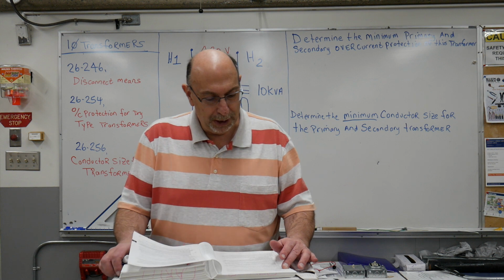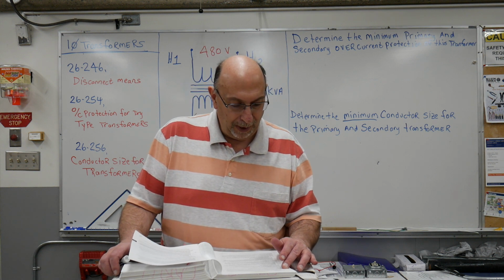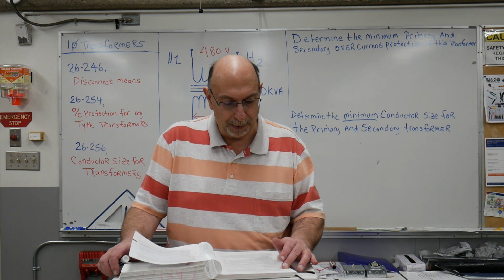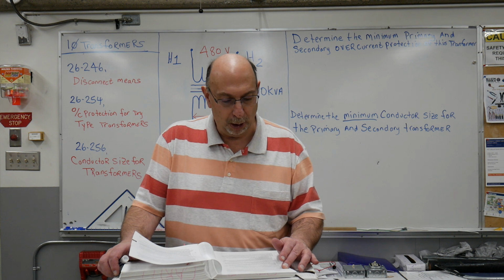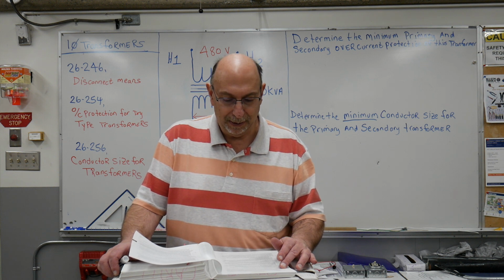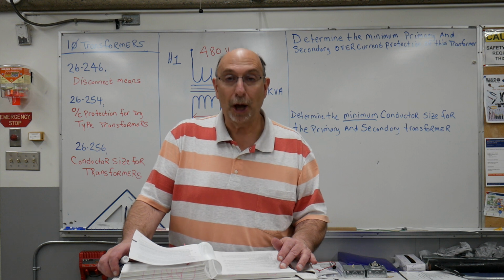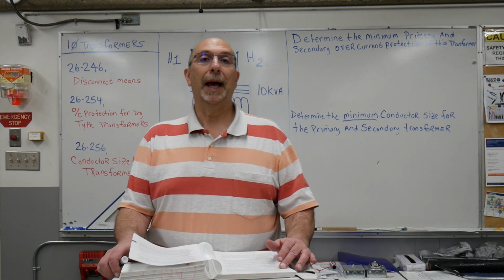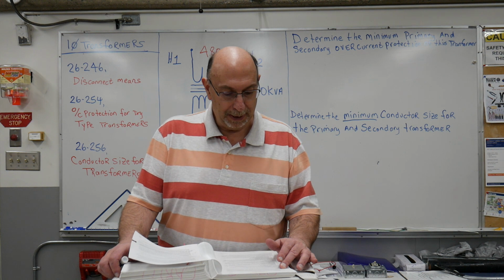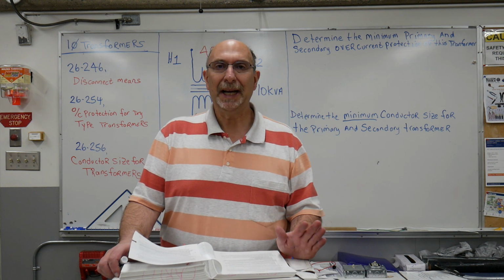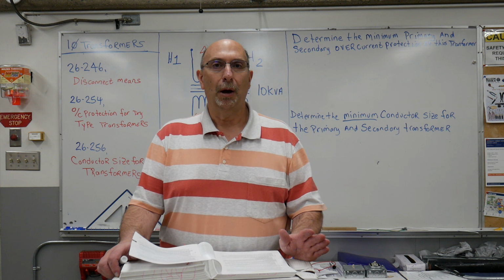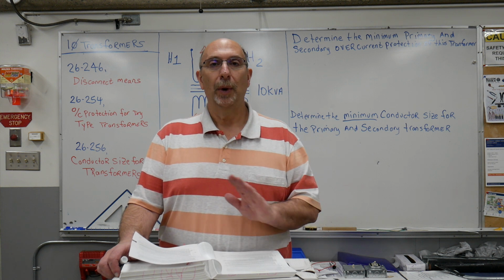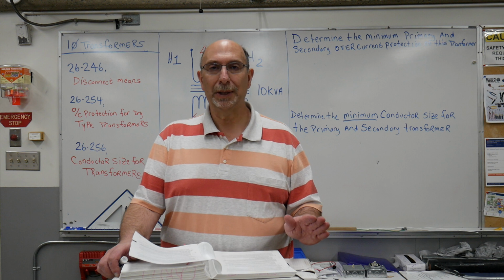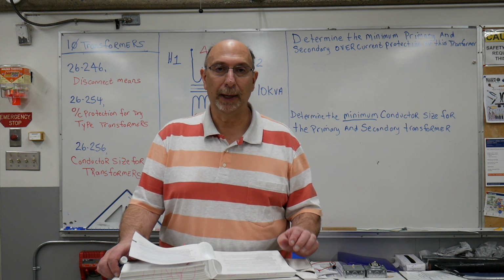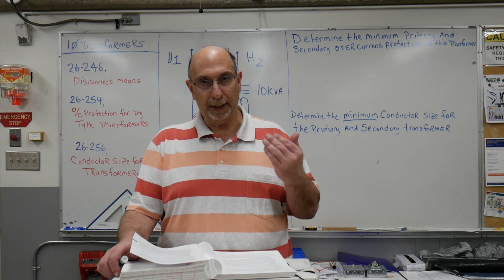We're not going to get into a unit substation, but subrule 2 talks about transformers being constructed so that all live parts are enclosed unless they are installed to be inaccessible to unauthorized personnel. Something like that could mean a vault, but we're not going to be dealing with a vault. 99% of the time the transformers are enclosed in some form of housing where you do not have any access whatsoever to the primary and secondary conductors, except if you take the covers off.